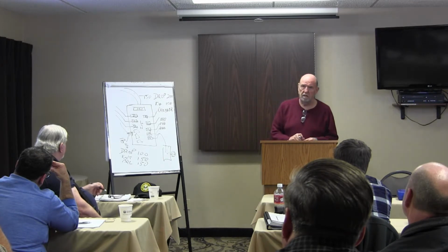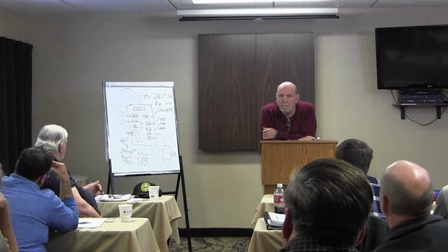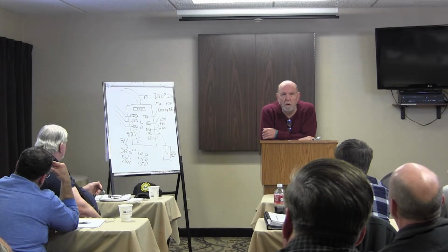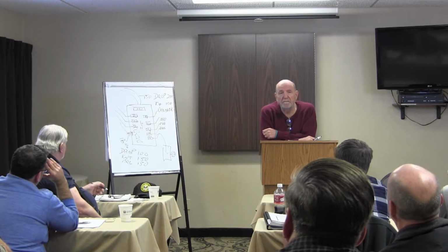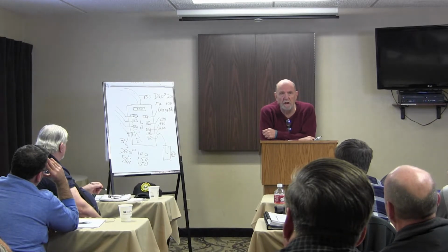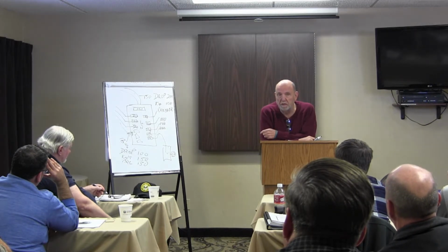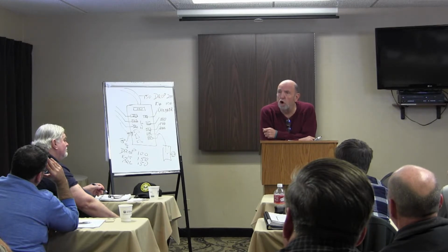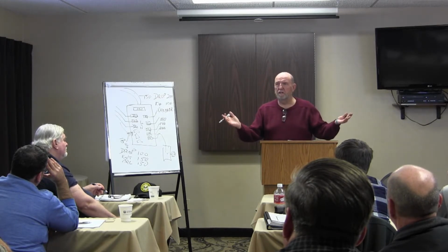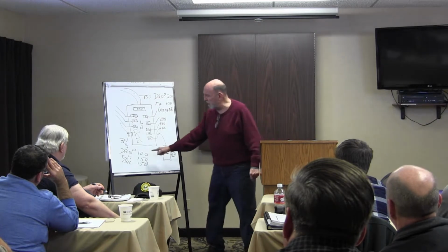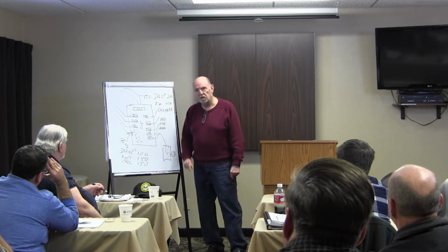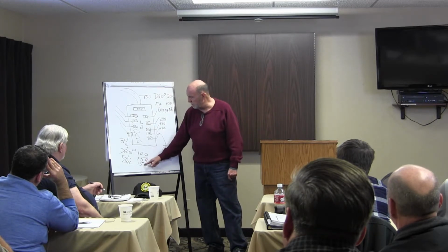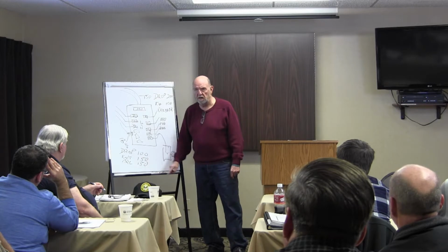So what's the defect? Breaker size wrong. How are you making that judgment? Breaker size should be the size of your smallest wire, because the house is defined by the smallest wire. Exactly accurate. You can't call the defect on the wire, because if the service size is defined by the smallest, then the smallest isn't the problem. The breaker's the problem. This breaker needs to be 100 amp.